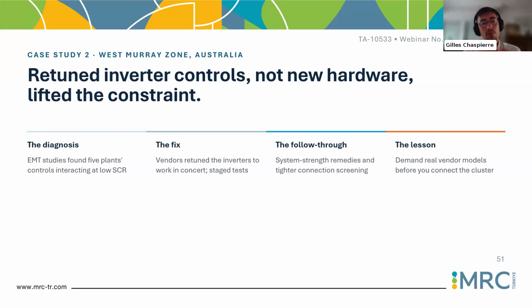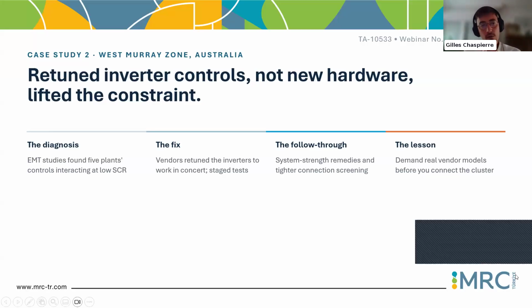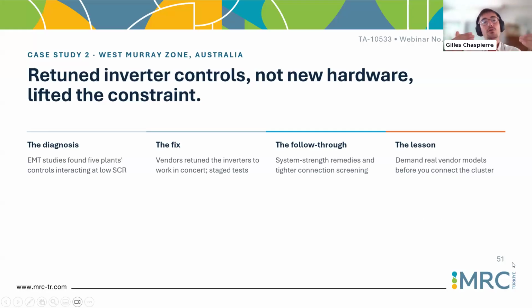So if you now enter a situation where your grid is weak, you need to do retuning, absolutely. The first step is retuning. Ask the vendor to do some checks, to do some studies to make sure that, only by software modification, the tuning can be made sufficiently more robust and this oscillation will disappear. Only when this is done, you can think: okay, I have made my tuning the most robust I can, but I still see oscillations, then you have no choice but a solution that reinforces your grid. Either adding new lines, or adding new assets, as we discussed, grid forming converters or synchronous condensers.